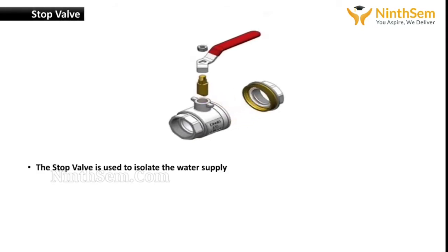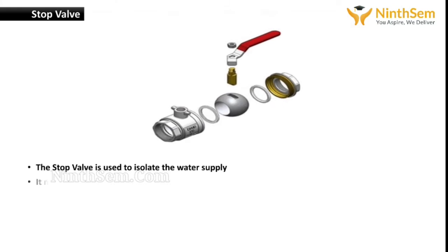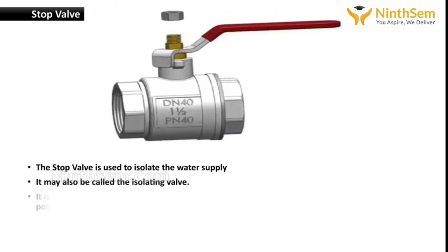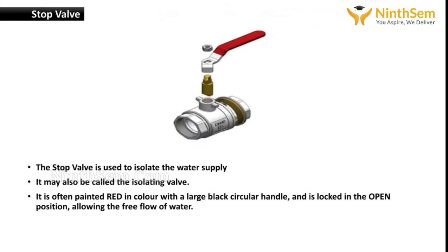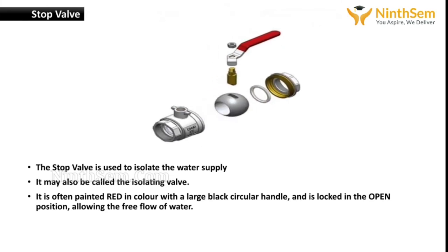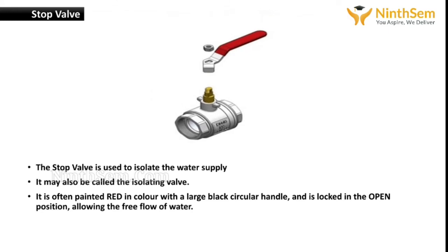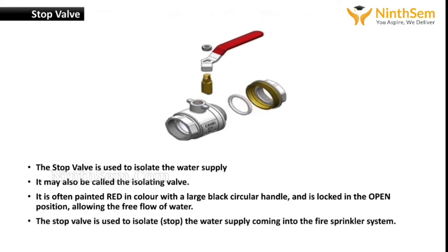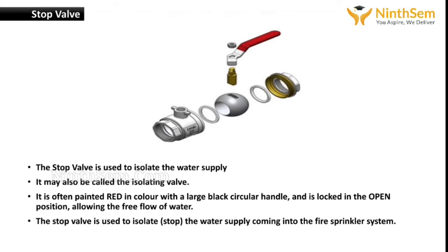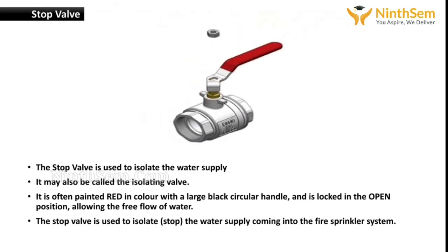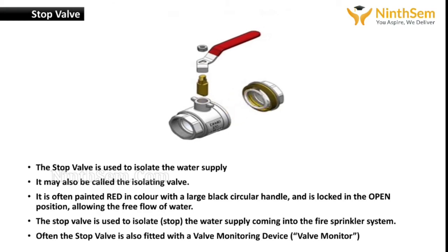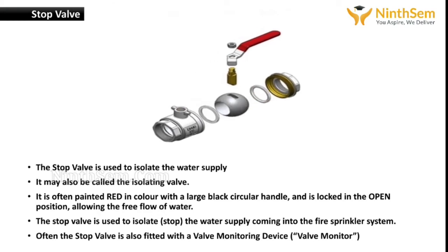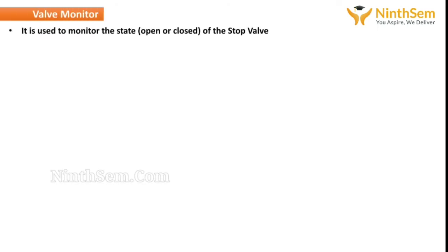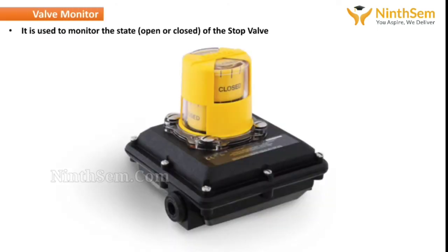So, stop valve. The stop valve is used to isolate the water supply. It may also be called the isolating valve. It is often painted red in color with a large black circular handle and is locked in the open position, allowing the free flow of water. The stop valve is used to isolate or stop the water supply coming into the fire sprinkler system. Often the stop valve is also fitted with a valve monitoring device. Next, the valve monitor. This is used to monitor the state, whether it is open or closed, of the stop valve.